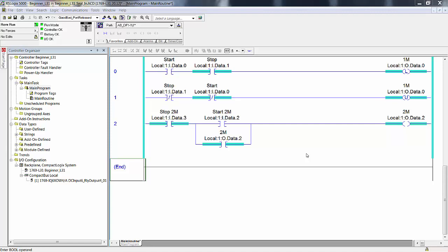Input 0, the very top one, is a special enhanced input in that the push button is wired in the circuit with a toggle switch, so when the toggle switch is off, then the push button is normally open. When the toggle switch is on, then the push button is connected as normally closed.